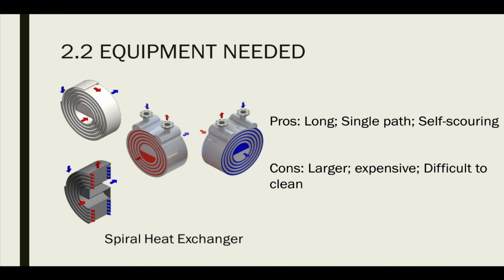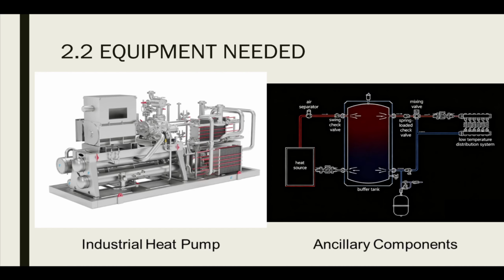And second, for spiral heat exchanger, the pros are a long single flow path that is ideal for slurries with solids, and a self-scouring action that resists fouling and clogging. And for cons, it's generally larger and more expensive than a PHE for the same duty, and cleaning can be more involved. After that, the industrial heat pump is a supporting component for upgrading low-grade heat, but it cannot handle the primary task of transferring heat directly from the dirty slurry stream. And ancillary components, like tanks and pumps, are essential for support. They don't perform the core heat exchange itself. This is why we selected the spiral heat exchanger as our core unit. It was the only option designed to handle our tough conditions.